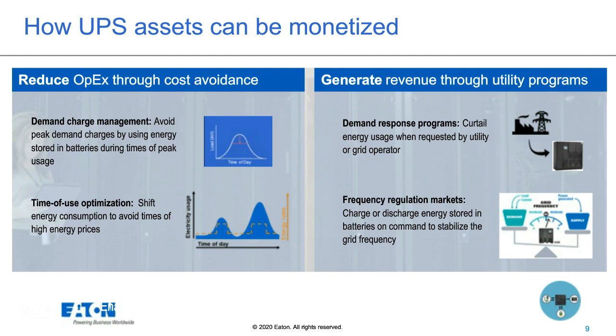Another one down in the corner is the frequency regulation market. If you think about the utility's incoming frequency, or your building at all, you know it's 60 hertz, at least in this part of the world. But during the times of day or times of year when the load is heaviest, the frequency tends to sag. Wouldn't it be nice if a UPS system, or many UPS systems together, could utilize their batteries and actually push power back onto the grid, back feeding the incoming power and pumping up that utility frequency and helping the utility company regulate it?